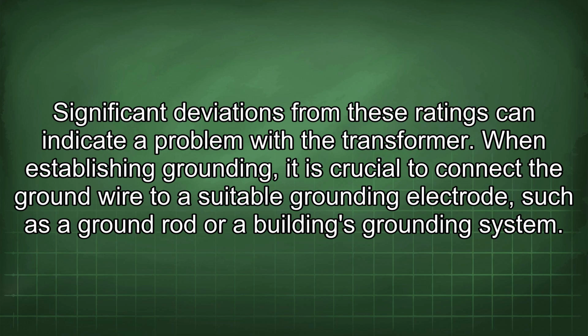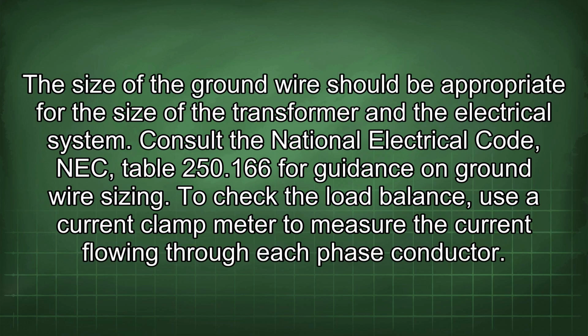When establishing grounding, it is crucial to connect the ground wire to a suitable grounding electrode, such as a ground rod or a building's grounding system. The size of the ground wire should be appropriate for the size of the transformer and the electrical system. Consult the National Electrical Code, NEC, Table 250.166 for guidance on ground wire sizing.